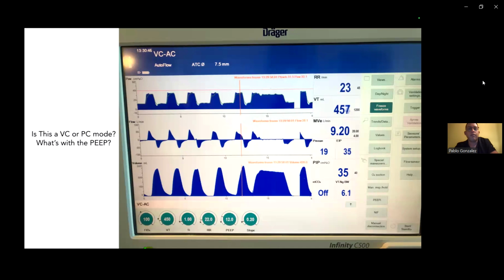Here you have volume control. It says AC volume control, but then as you can see, there's autoflow and there's some automatic tube compensation on this ventilator. So is this a volume control or a pressure control mode family? And what's with the PEEP? So the PEEP keeps deflecting down.